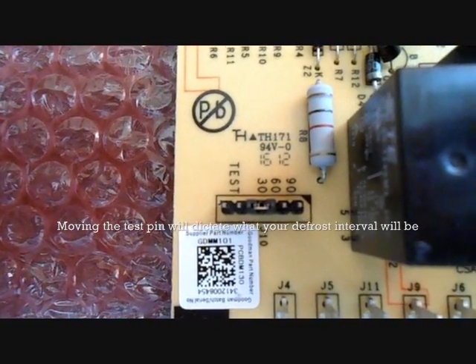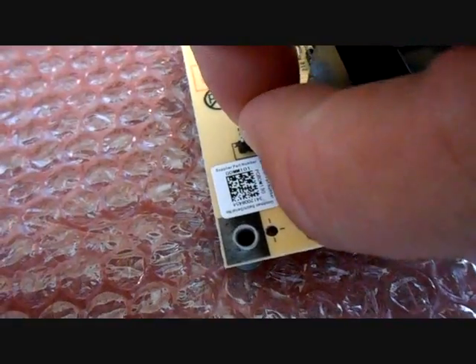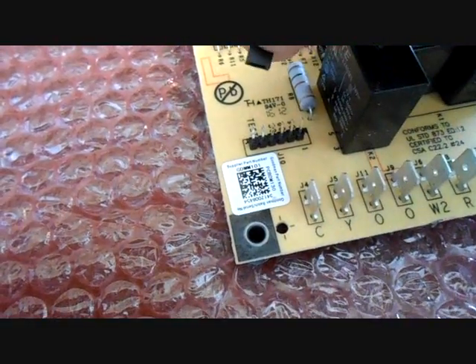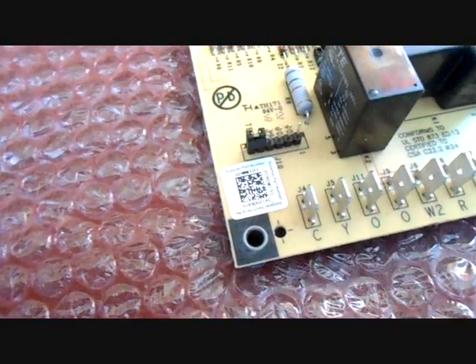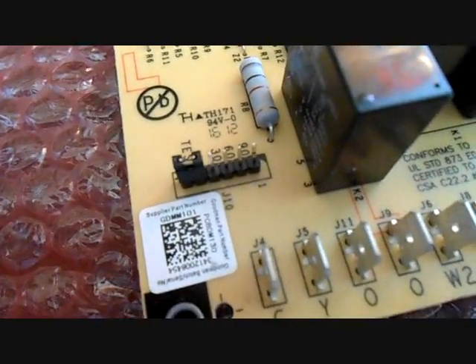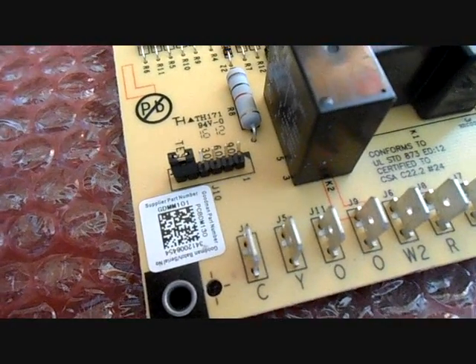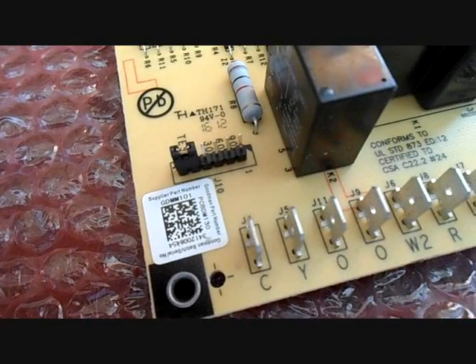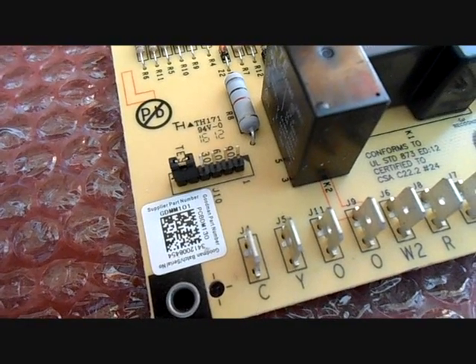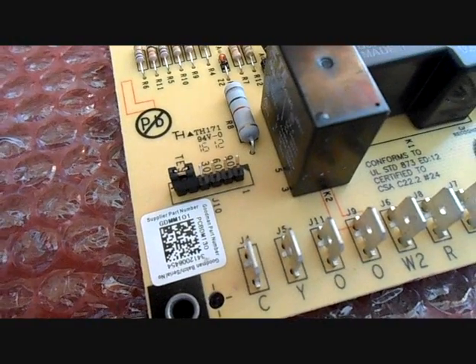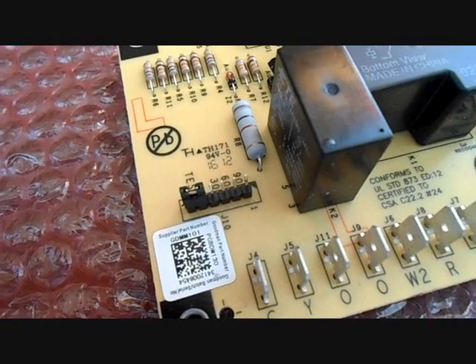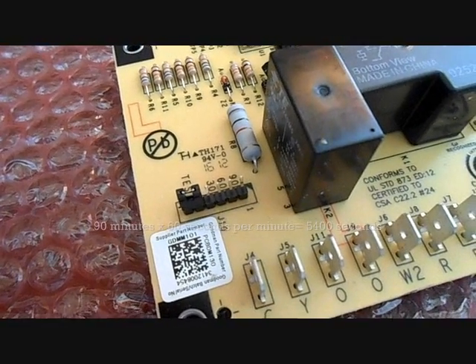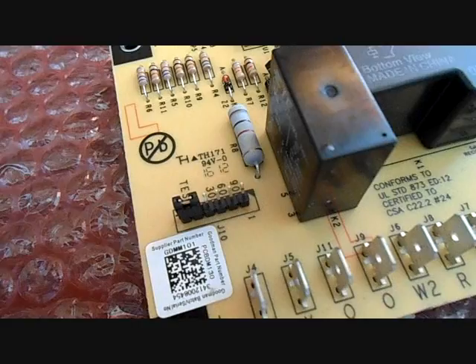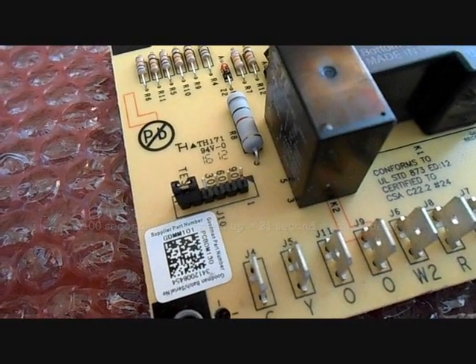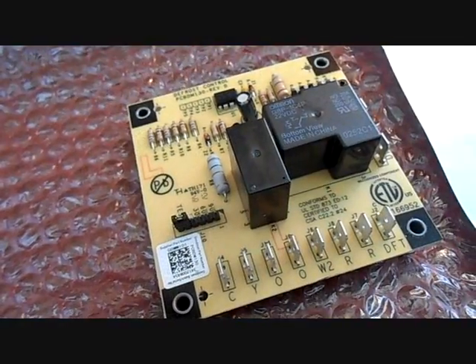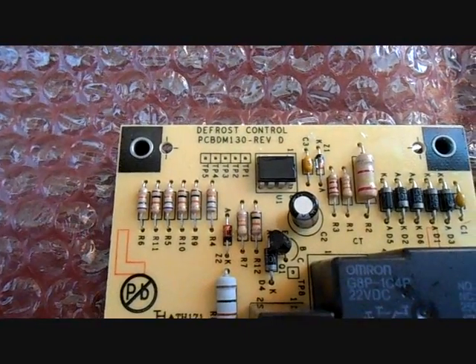On the very end, you see a test pin. You will slide, see here, there's a little pin down here. There it is. Take it off, put it on test. It doesn't immediately go into defrost. It can take up to 21 seconds to go into defrost. Basically, this speeds up the interim, your 30, 60, or 90 minute interval. I think it speeds it up by a degree of 256 times as fast. So under a 90 minute interval, that will entail that it could take up to 21 minutes. Doesn't mean it, or 21 seconds, sorry. Doesn't mean it has to, but it can. So make sure you use some patience when you're testing it. Give it the right amount of time. And that is the Goodman defrost board number PCBDM130.